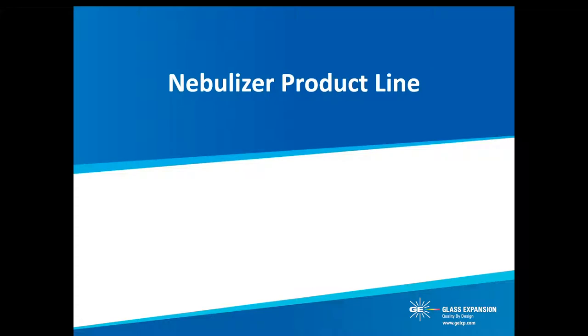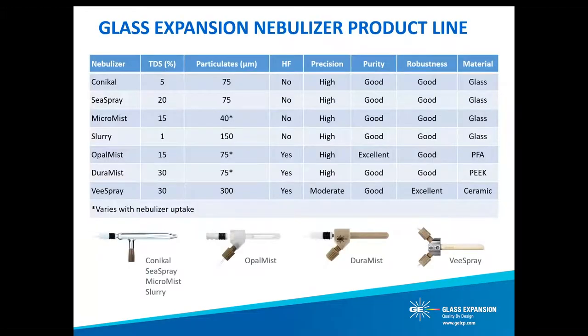Now that we have introduced our unique design advantages, let's begin the review of Glass Expansion's nebulizer product line. Glass Expansion offers the largest range of concentric nebulizer designs by any manufacturer. Each of our models is ideally suited for a specific application or range of applications. This table briefly highlights the material tolerance and performance criteria of each nebulizer model. When choosing a nebulizer, key selection criteria should include nebulization efficiency, purity, tolerance to hydrofluoric acid, particulates, and total dissolved solids — referred to as TDS throughout this presentation.